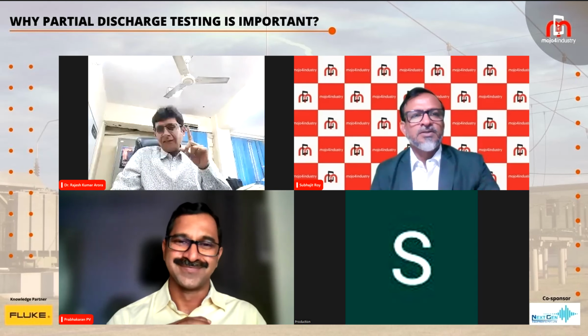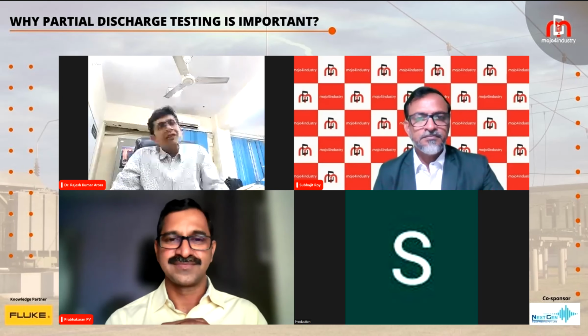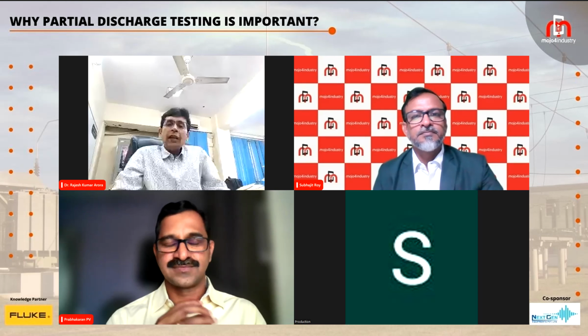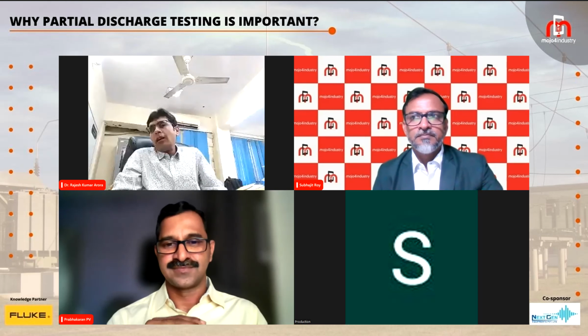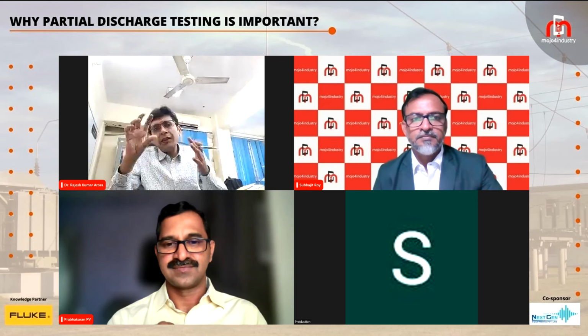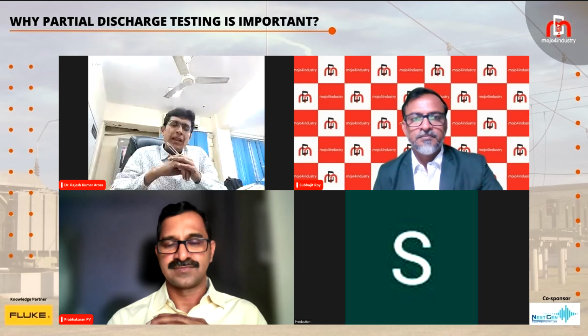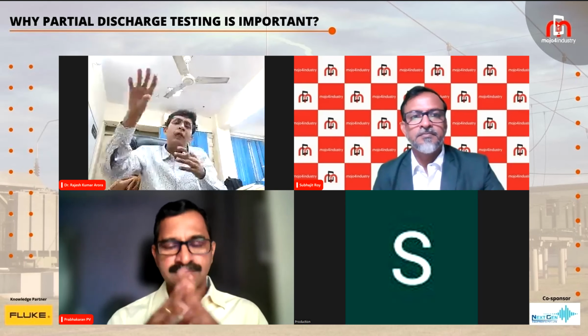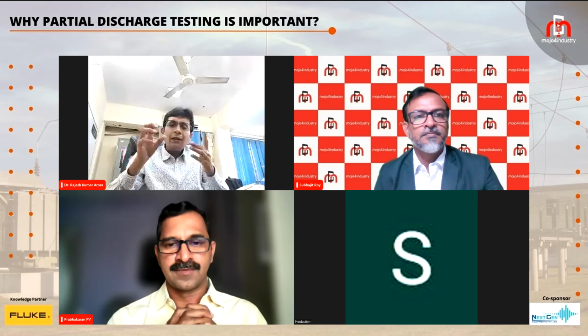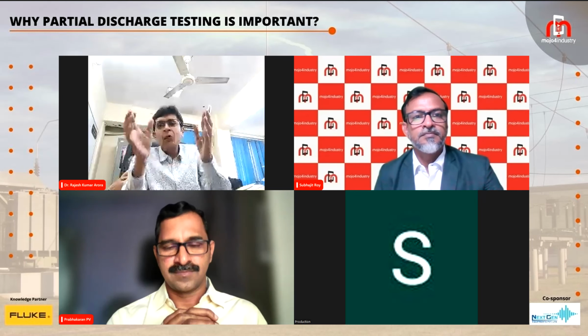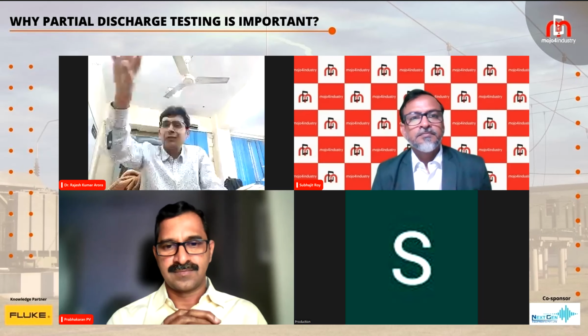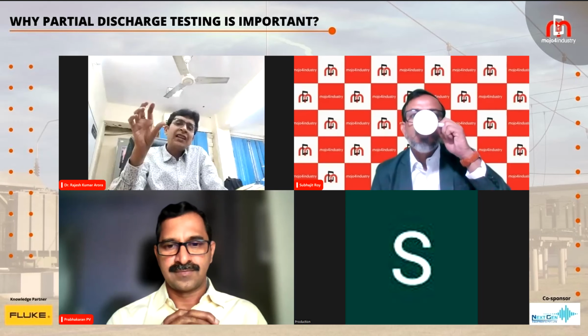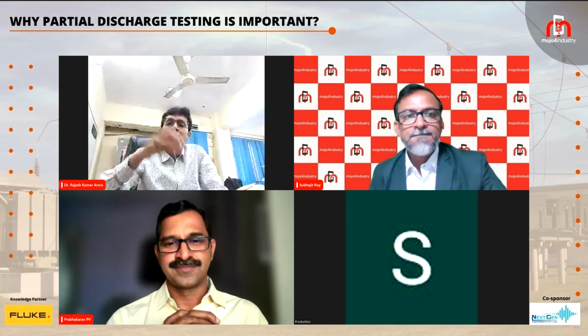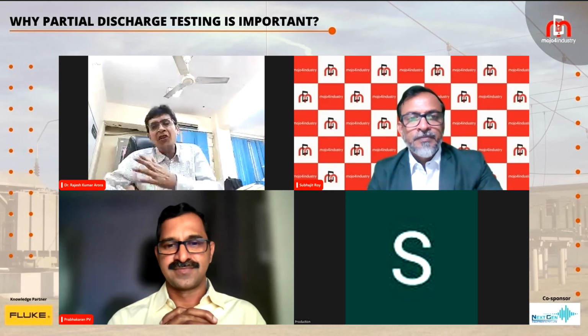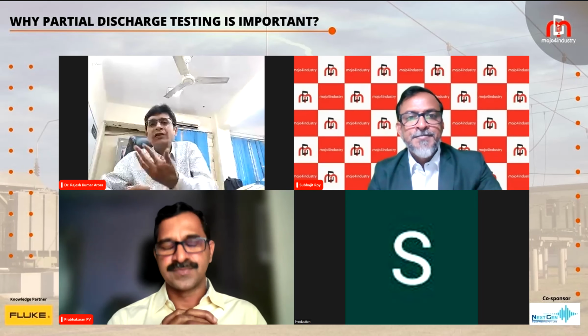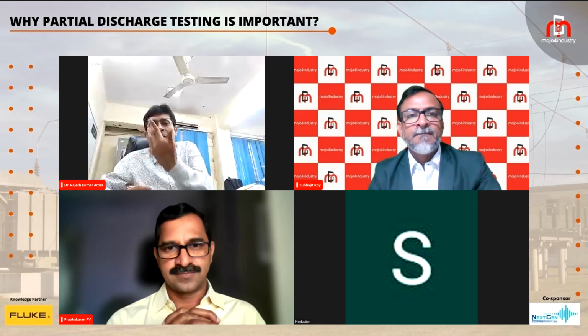Yes sir, I'd like to share my experience. When using acoustic measurement for partial discharge online, you first identify the fault in a coarse manner, then fine-tune it by reducing the spacing between external sensors on the equipment. This way you get a pattern, and based on that pattern, you can differentiate whether it's due to voids, external particle protrusions, or something else.